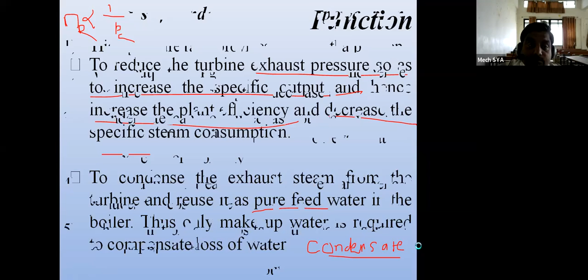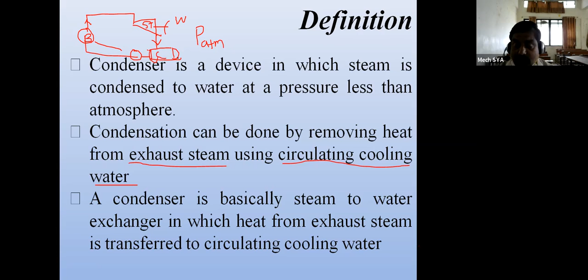Condensers are a device which condenses steam into water at pressure less than atmospheric. Condensation can be done by removing heat from exhaust steam using circulating water. Exhaust steam means the steam coming from the turbine, therefore it is called exhaust steam. The condenser is basically a steam to water exchanger, in which heat flux from exhaust steam is transferred to circulating cooling water. It is used to reduce the turbine exhaust pressure so as to increase plant efficiency and specific output. Condenser pressure is inversely proportional to Rankine cycle efficiency.